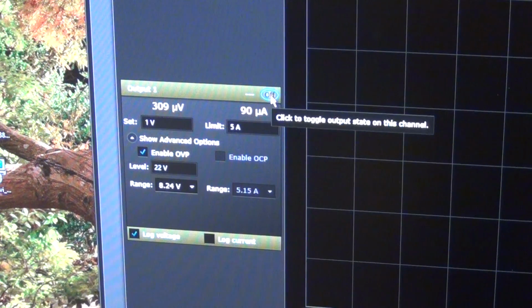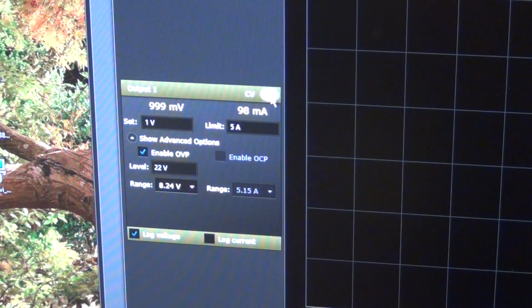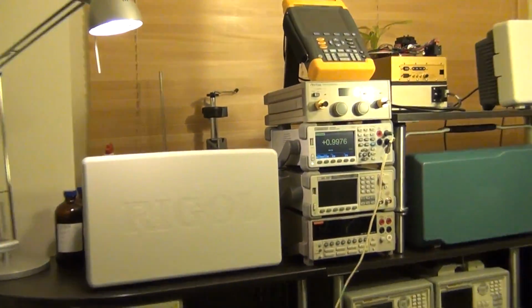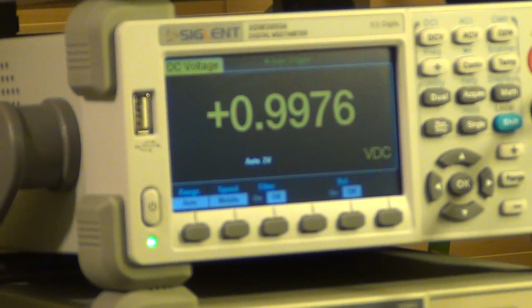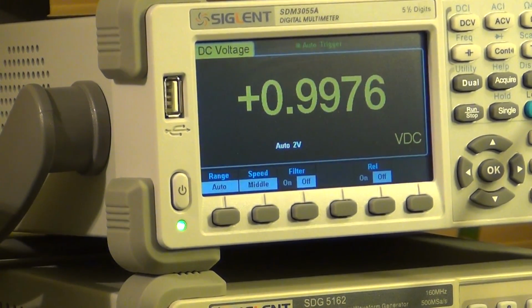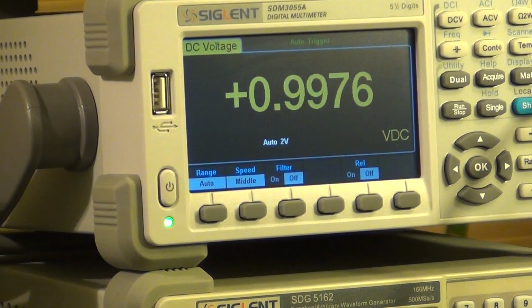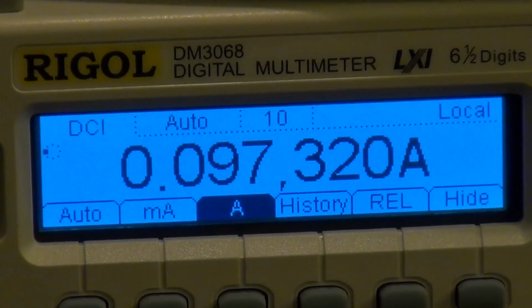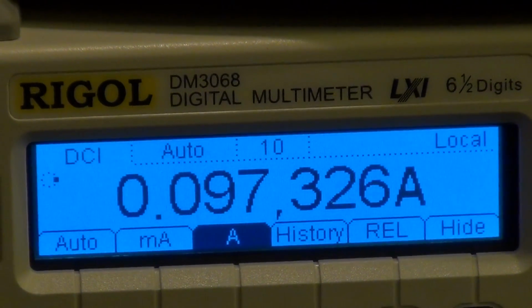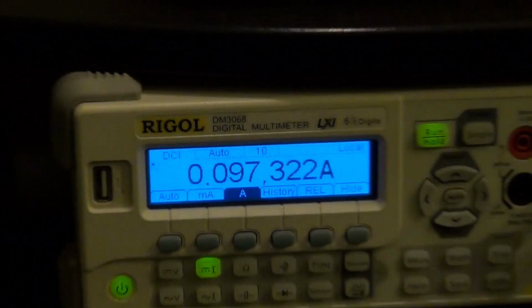How do I turn it on here? Oh, there we go. Here it is. Turn it on. It says it's measuring. Oh my goodness, look at that. How is that for awesome? Here's the supply voltage, 0.9976. The computer is reporting 1 volt, which is very close. And it's supposed to be 100 milliamp, and it's 97.3. That is brilliant. So the supply is actually working.